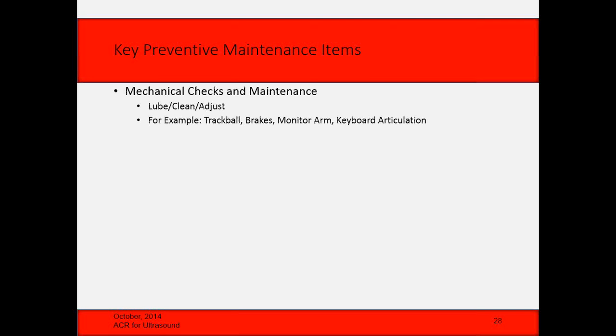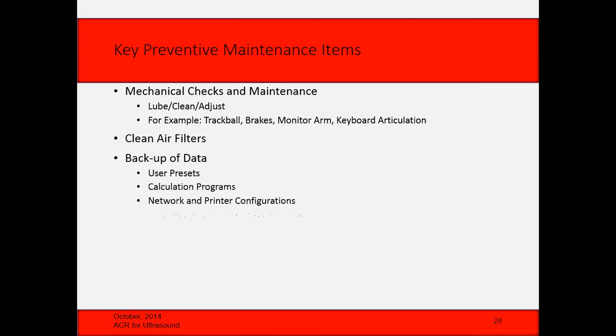So some of the key items: mechanical checks and maintenance, so lubing, cleaning, adjusting, cleaning the air filters. Of course, the users need to be doing this on a regular basis. Most of these systems really need to have the air filters cleaned quite regularly, especially in some facilities where it's dusty. Backing up the data. This is what I say should be done in PMs. The ACR actually doesn't specify anything. So some of the things should be done: backup user presets, the calc programs, and I always leave one with the system and one to keep in the biomed shop or one to take back with me.